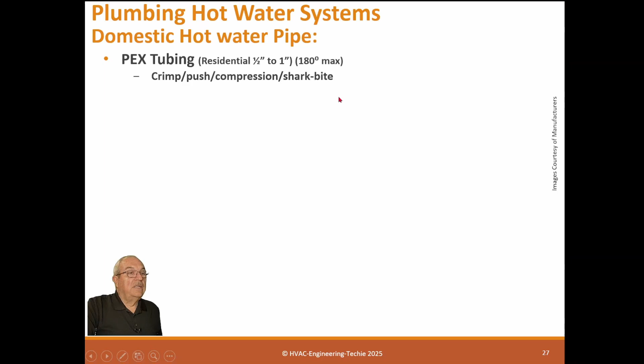So domestic hot water pipe: PEX tubing again, 180 degrees max, 1/2 to 1 inch, crimp, push, compression, shark bite fittings. Copper pipe type L, K, L, or M with wrought copper fittings, solder, braze, compression, or crimp joints. Galvanized steel pipe with galvanized steel fittings, threaded or groove joints, 1/4 to 24 inch, big pipe. Stainless steel pipe, schedule 40 or tubing. And the copper pipe is 1/4 to 6 inch normally. 6 inch is really expensive, by the way.